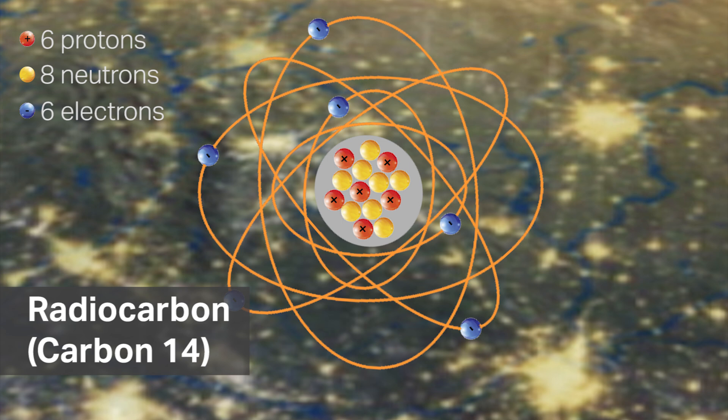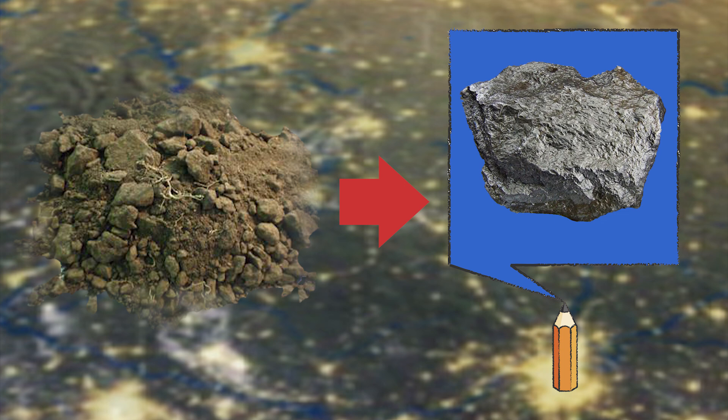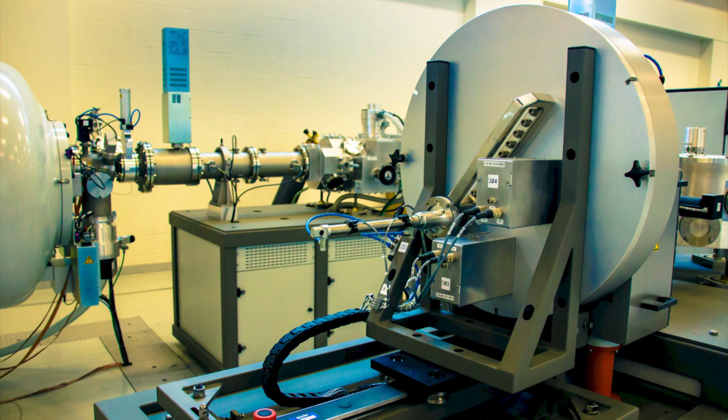What we do is we take any sample and convert it to graphite. There's a little aluminum button with the graphite in the center of it. We can mount up to 200 of these graphite targets into a cartridge type we call an ion source, because what we're going to do is take the atoms of carbon in that graphite and convert them to ions. We're going to ionize them.